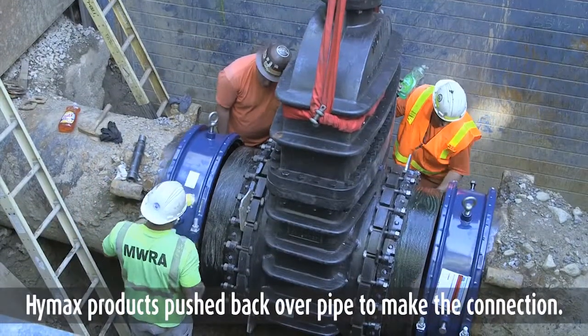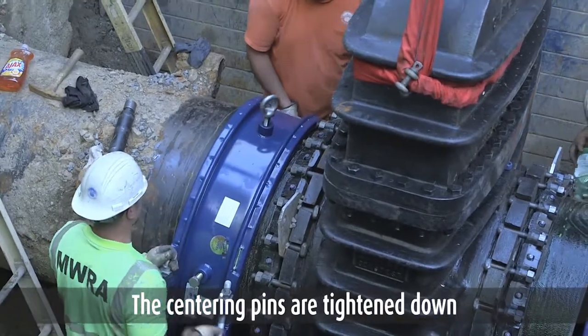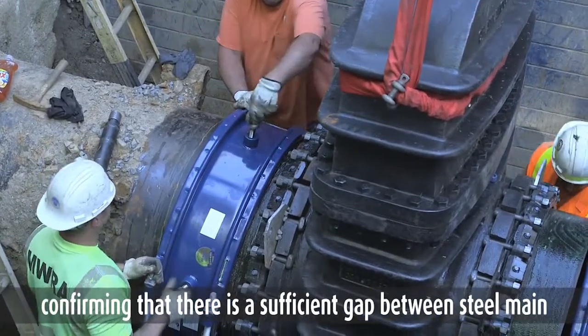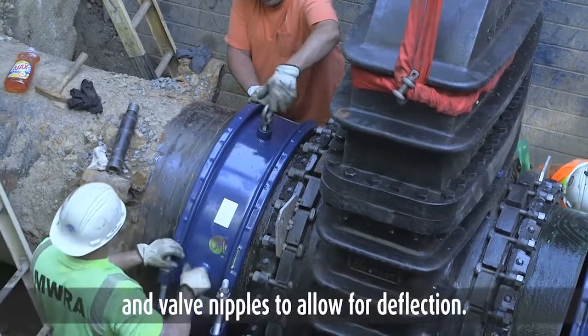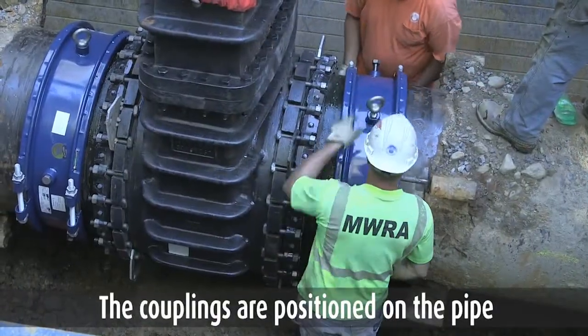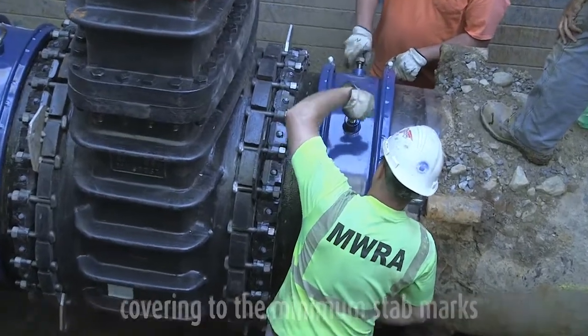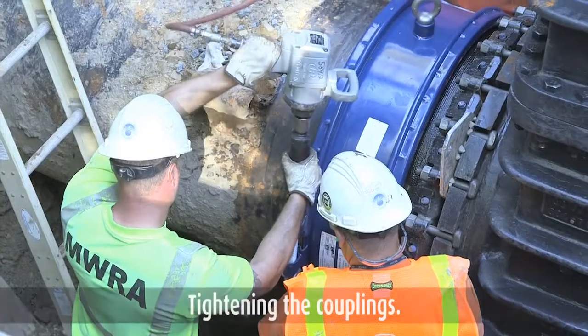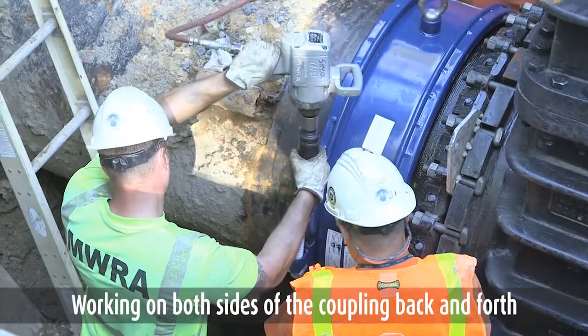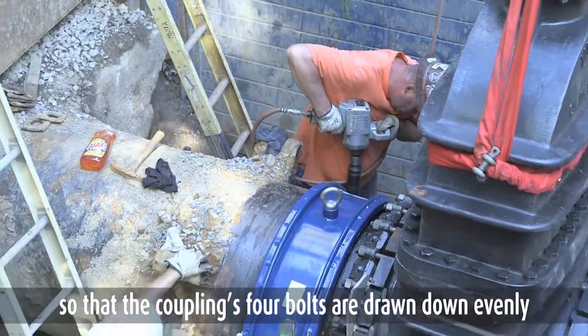The Hymax couplings are pushed back over the pipe to make the connection. The centering pins are tightened down, confirming that there is a sufficient gap between the steel main and valve nipples to allow for deflection. Tightening the coupling, working on both sides back and forth so that the coupling's four bolts are drawn down evenly.